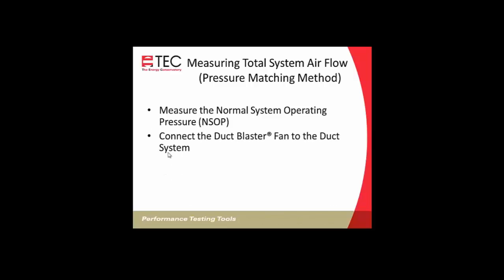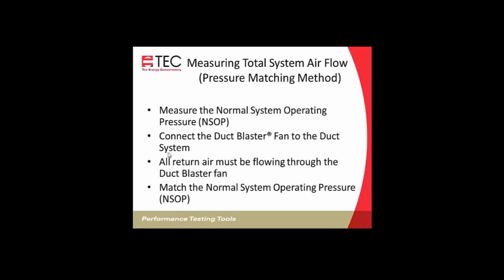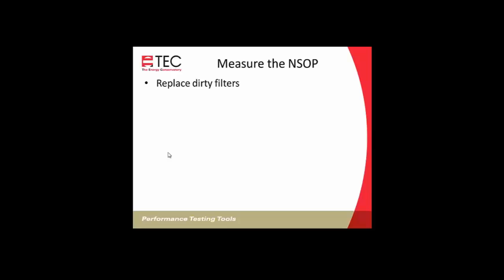You'll want to connect the Duct Blaster fan to the duct system. And you want all the return airflow to be flowing through the Duct Blaster. So if you're attaching it right at the air handler, you're going to need to block off the return side. So all of the airflow that you're measuring needs to be going through the Duct Blaster fan. And then we'll turn on the Duct Blaster fan to match the normal system operating pressure, and then measure the flow through the Duct Blaster.